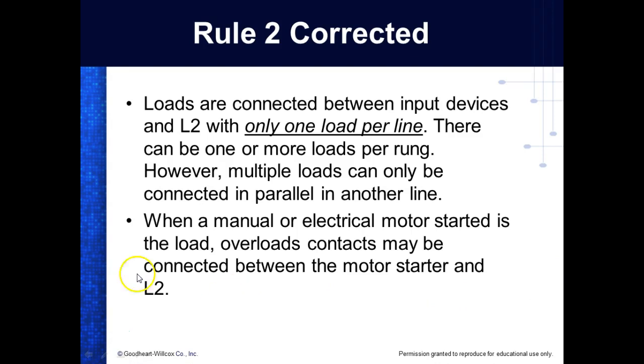This is not what disconnects it, these are the sensors that sense the overload. We have a contact in here that we put into our ladder diagram to disconnect the motor through its control circuit. That symbol is the only thing allowed between the load and L2, the heater contact. Let me draw the actual diagram.